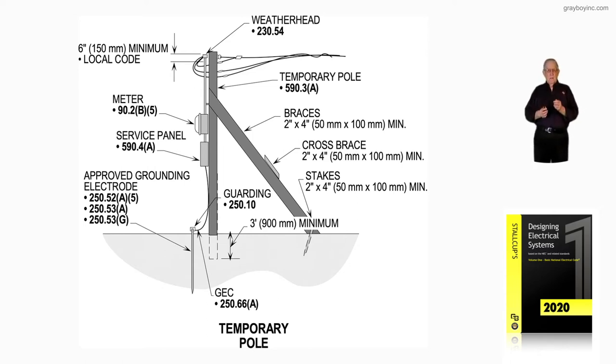And the service equipment. Notice in Article 590 — I believe it's 590.3 — service equipment has to be installed exactly in accordance with Article 230, but the rest of the wiring for the construction period can be less than what the code would require. Notice you have a service panel there, 590.4A. The meter is 90.2(B)(5).